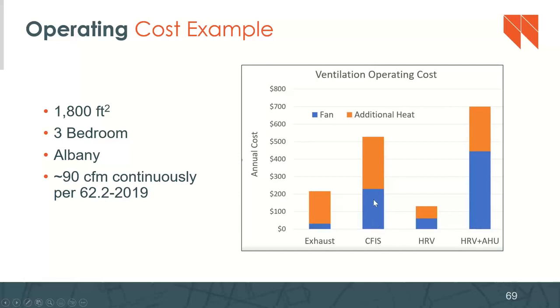For that central fan integrated system, because in this example it was using the actual air handler fan, you can see the electrical energy is quite high. And then, of course, the additional heat for this system is pretty close to the exhaust-only system, if not exactly equal, right? You still have to condition that ventilation air with your heating and cooling equipment. With an HRV, you can see it's the lowest of both, for both the fan and the additional heat, because there is heat recovery. The cost of moving the air is greater than the exhaust-only example, but you make up for any additional costs when you compare the HRV. That additional heat, because there is energy transfer, is reduced.